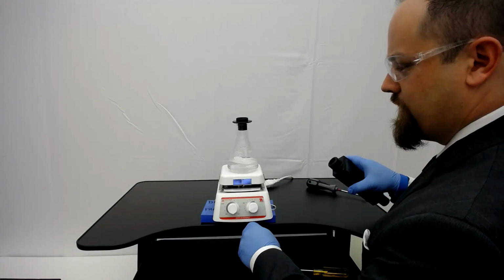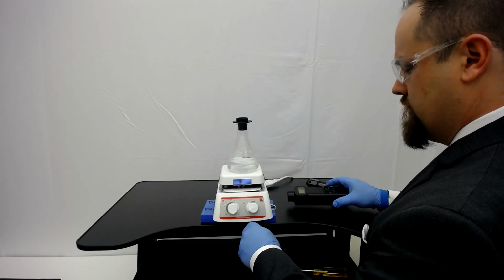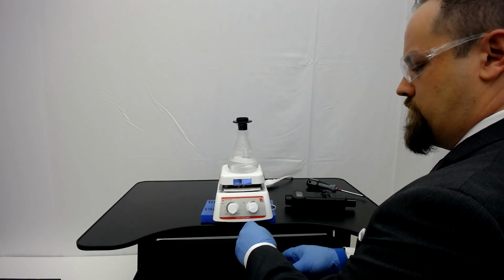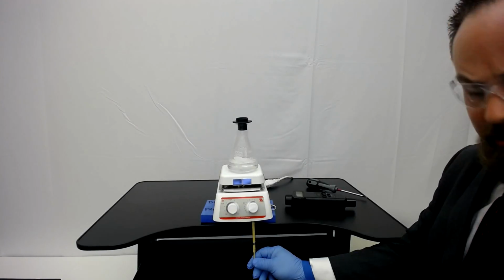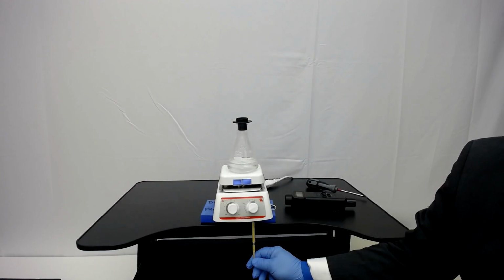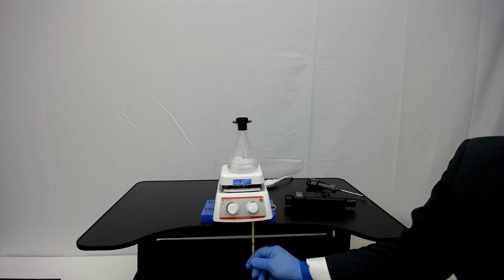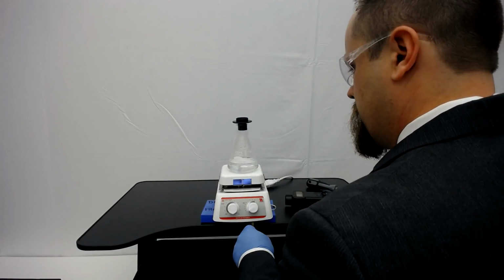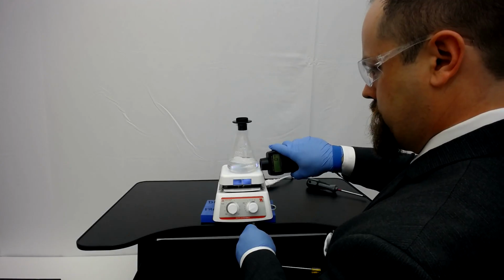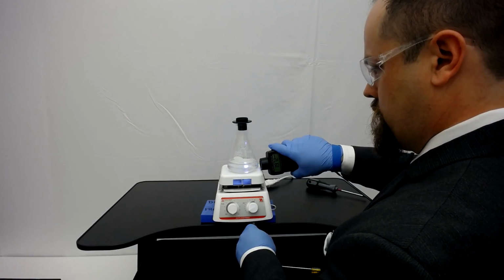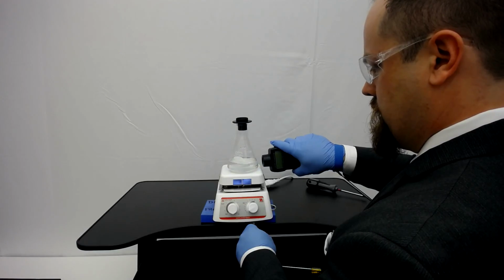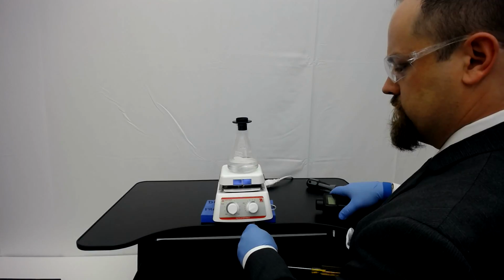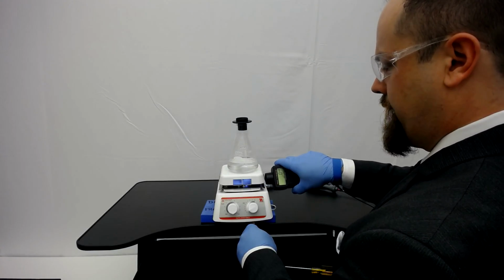Now, as that stir bar spins, the tachometer is getting 2 pulses, so you have to cut what the tachometer says in half. What we're looking for is for the unit to be between 50 and 250 RPM. So we're cutting that 399 in half. So that's about 200 RPM. It's a little bit fast for this.